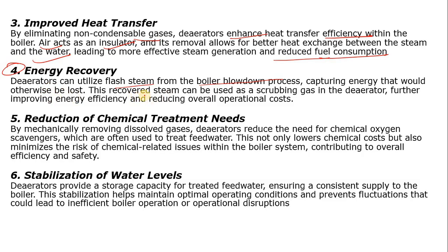This recovered steam can be utilized as scrubbing gas in the de-aerator, further improving energy efficiency and reducing overall operational cost. Fifth, reduction of chemical treatment needs: by mechanically removing dissolved gases, thermal de-aerators reduce the need for chemical oxygen scavengers, lowering chemical cost and minimizing the risk of chemical-related issues within the boiler system. Sixth, stabilization of water levels: de-aerators provide storage capacity for treated feed water, ensuring a consistent supply to the boiler and preventing operational disruptions.